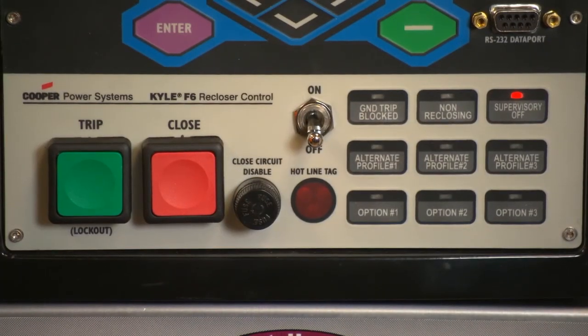Protection profiles. 4 protection profiles capable of fully specifying control operation are standard in the control. Each protection profile includes the following as a minimum: overcurrent protection, over-under voltage protection, over-under frequency protection, directional protection, hotline tag functionality, sync check, sensitive earth fault protection, sequence coordination, and operation settings.